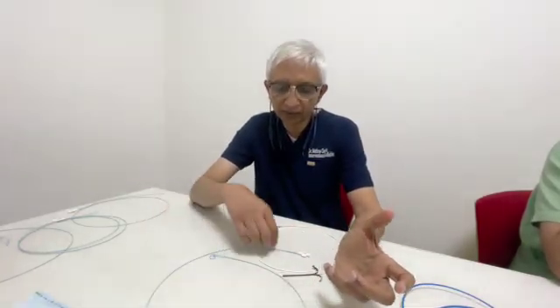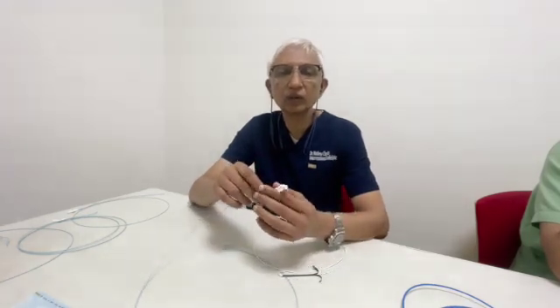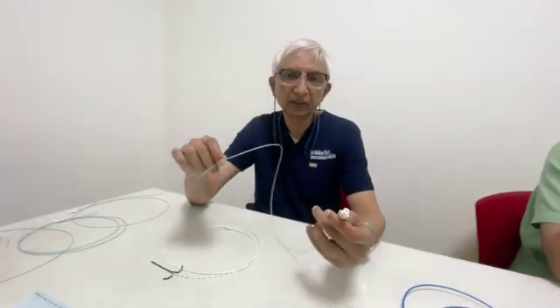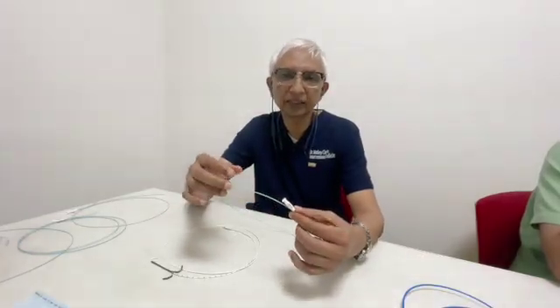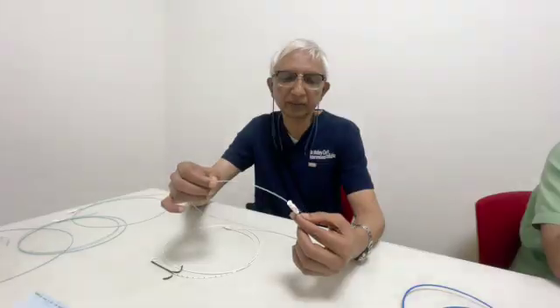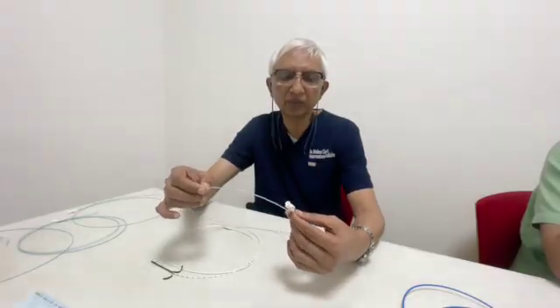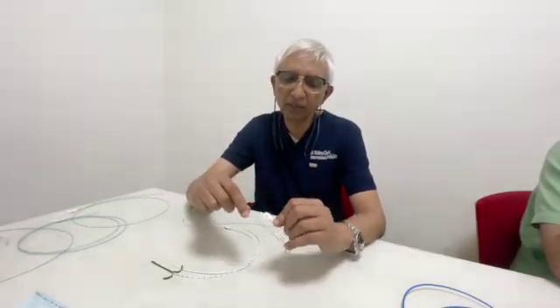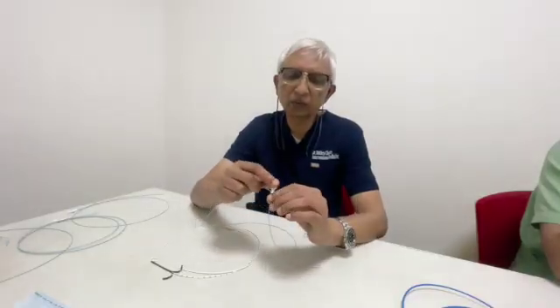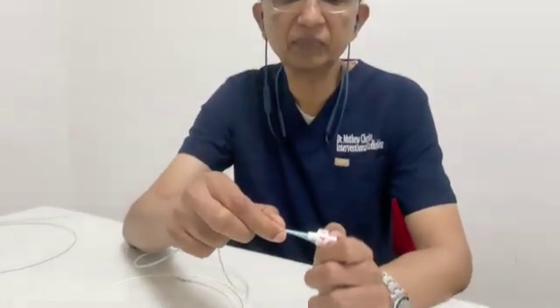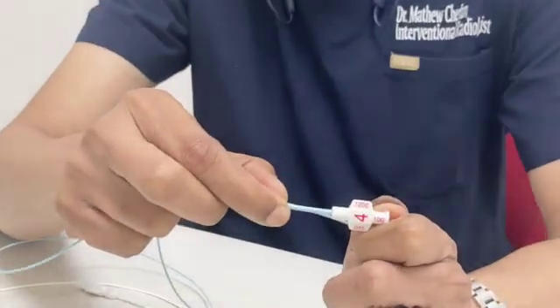Thirdly, also remember the length of the catheter determines the length of your guide wire, and it's also important when you want to exchange that catheter for something else. For example, if you've got a 100 centimeter catheter, which is the commonest size, your guide wire length should ideally be at least 180, so that you've got enough length to exchange the wire. 200 is even better. Okay, you get that point? So, there are a couple of things you have to look at. Also, there is a number written here, 1200, which basically means the pressure that it can take before rupture.